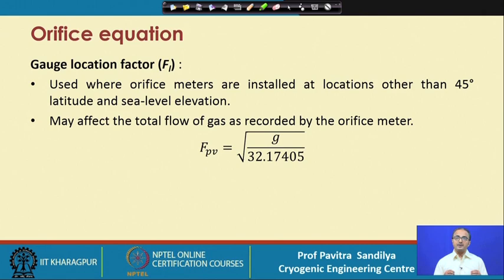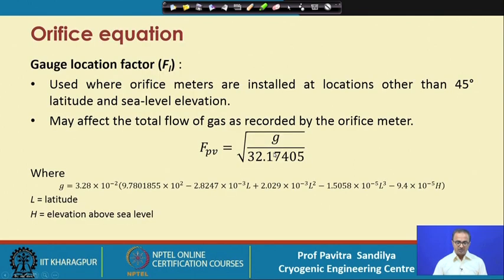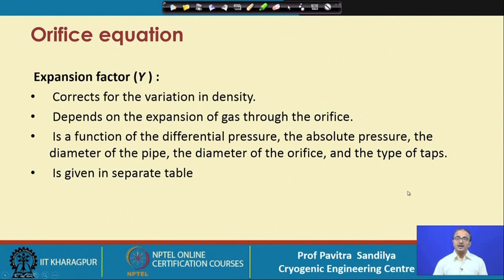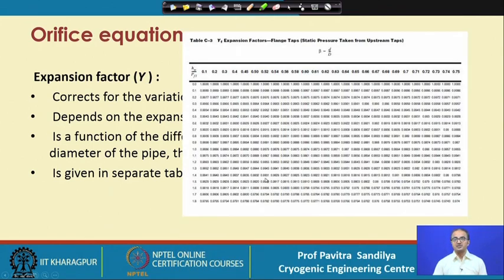Depending on the latitude and elevation at which the gauges are located, there is also an effect on metering. A correction for gravitational acceleration is given by an equation where L is the latitude and H is the elevation above sea level. The expansion factor corrects for density variation and depends on how the gas expands through the orifice — it is a function of differential pressure, absolute pressure, orifice diameter, pipe diameter, and type of taps, obtained from tables in the literature.